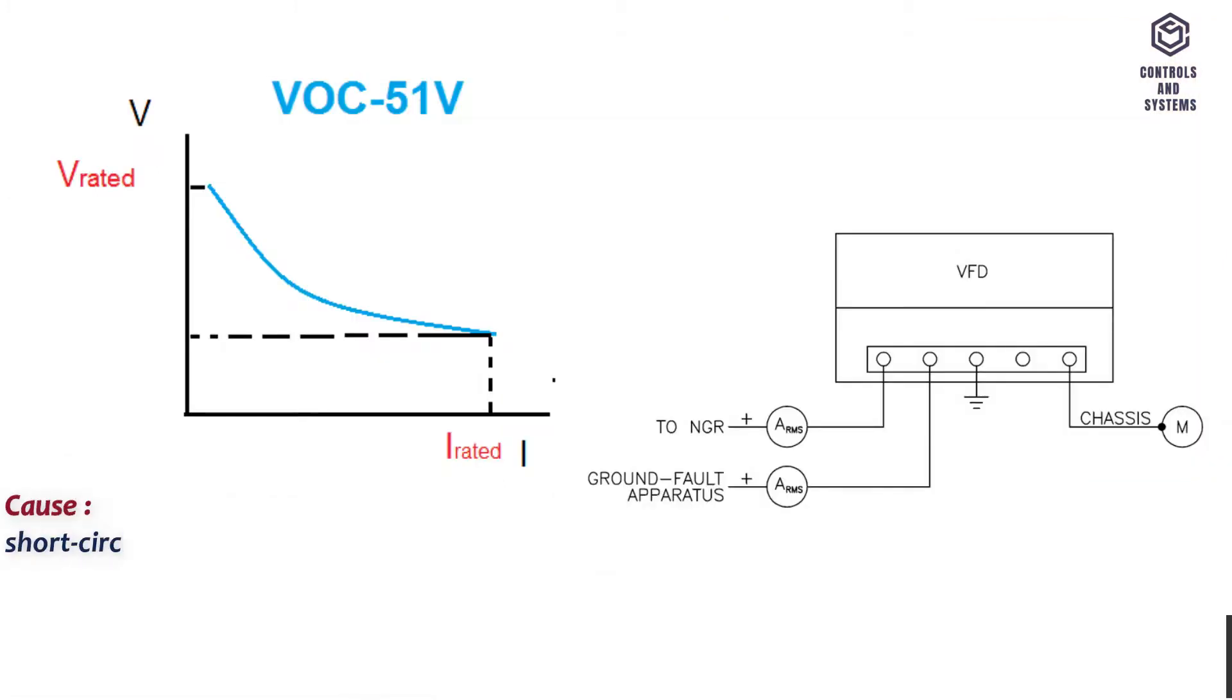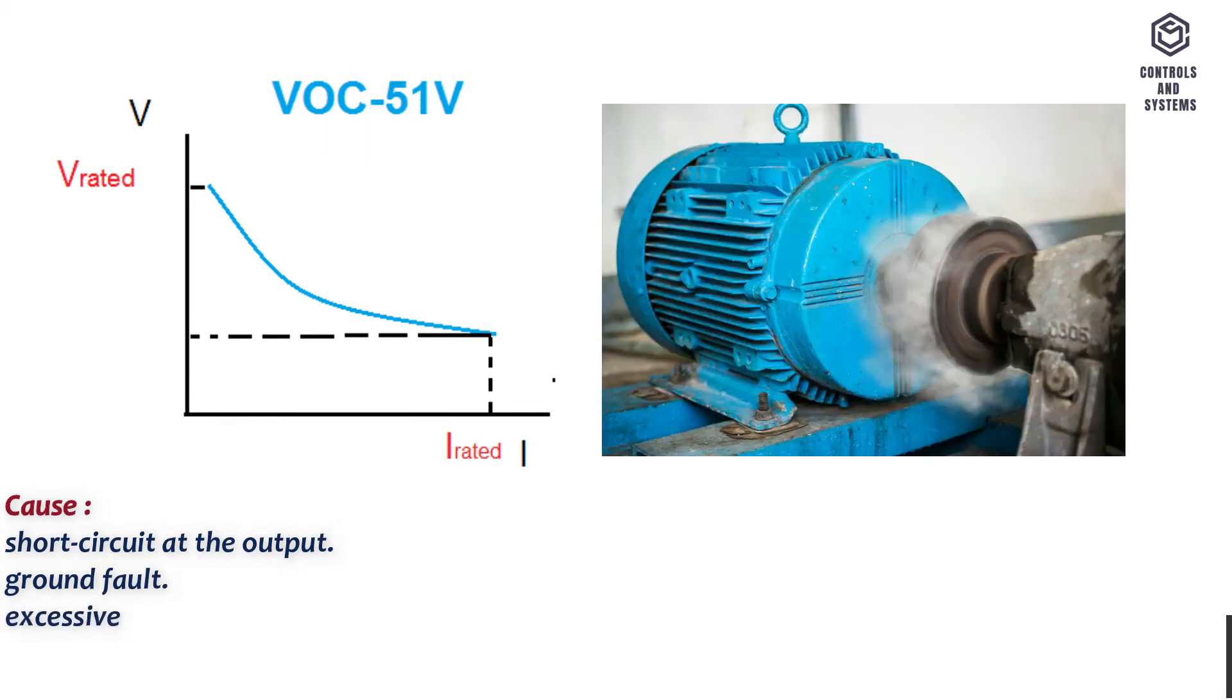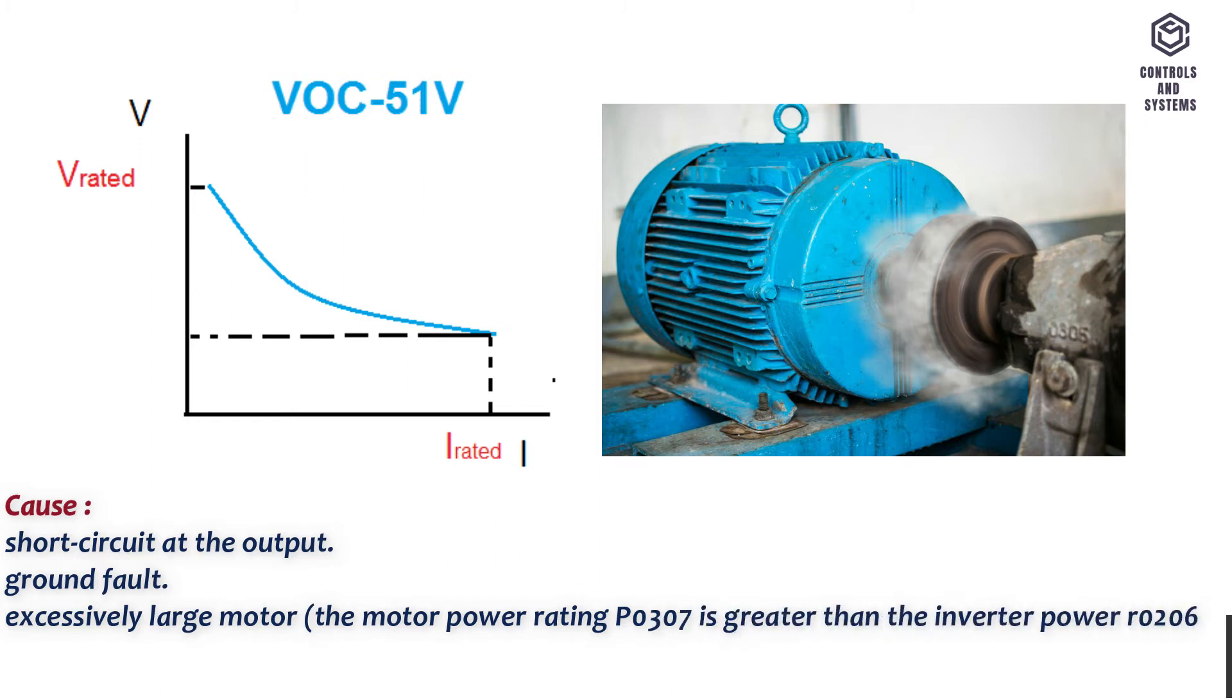Cause: Short circuit at the output. Ground fault. Excessively large motor, the motor power rating P0307 is greater than the inverter power R0206. Defective final stage or end stage.